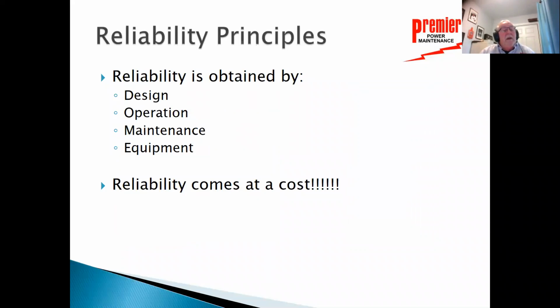So let's look at the design. If you have the opportunity to be part of that design, then we need to actually be able to design a system where we have multiple components that are parallel in nature. We need to operate our system so that every single component is operating within its standard design limits. We need to maintain that equipment to the point where we can expect several more years out of it. And we need to do a really good job of what we are actually purchasing when we purchase that equipment. Low cost, low bid is not necessarily the most appropriate thing to do when we're talking about trying to develop a reliable electric system.